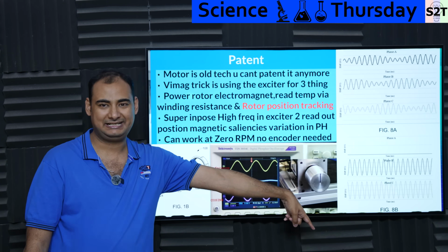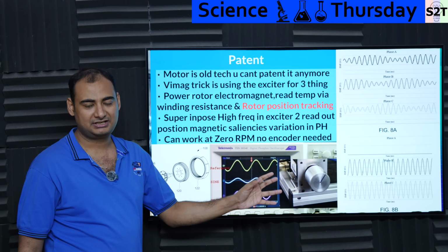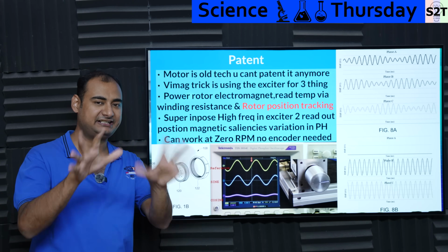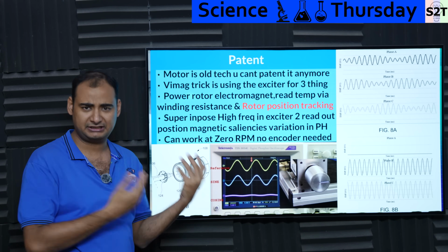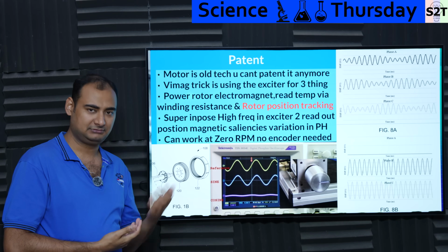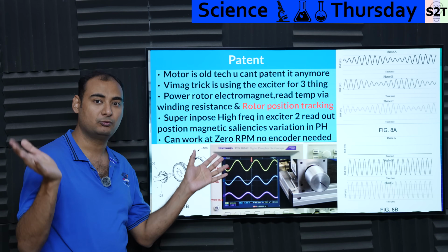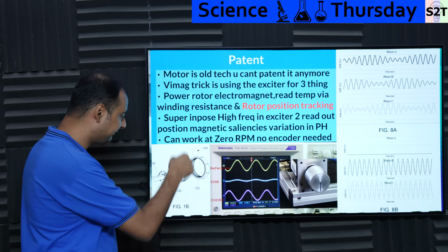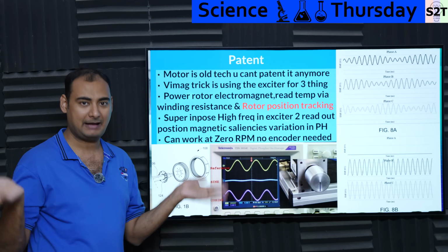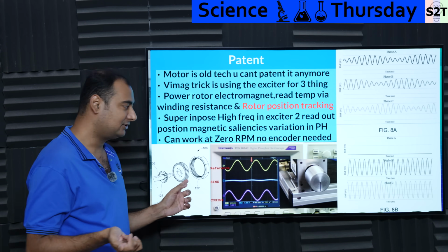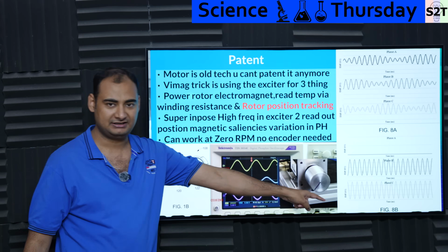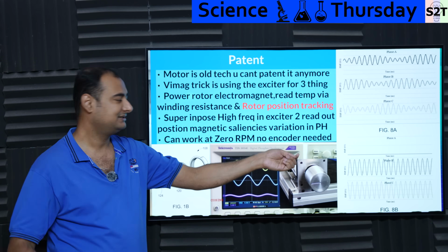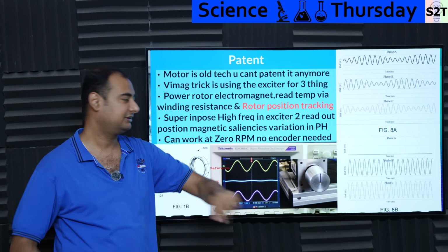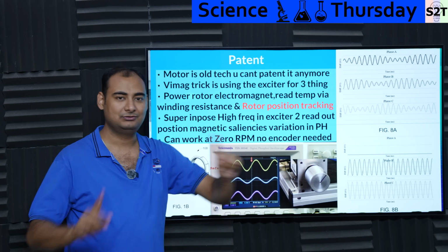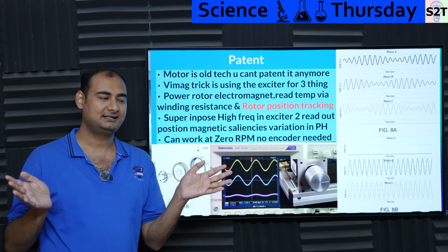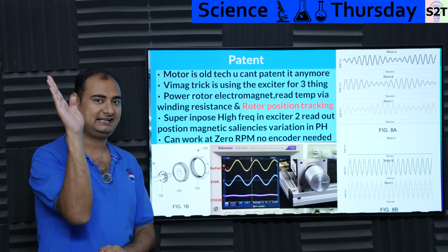This happens, which we call figure 8B. What it's doing is the stator part screams a high frequency signal onto the carrier frequency. At zero point it may not have the base current, so it's just figuring things out, waking up the system. It screams high frequency, which goes into the rotor and bounces back. Every magnetic system does that. When it bounces back, you read all the phases. Because you injected the high frequency, one phase where the alignment is perfect will give zero line, no data. The other two will be 120-degree offset signals. Ta-da, you know the exact angular position.